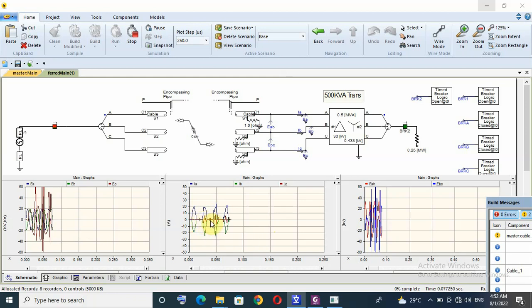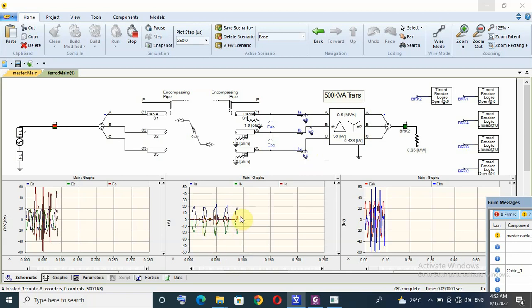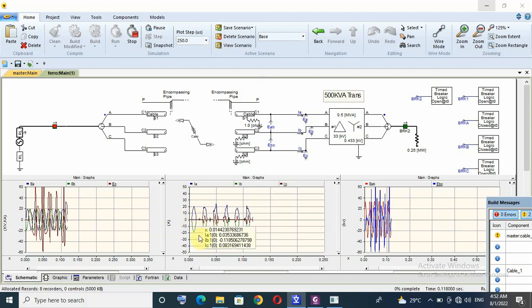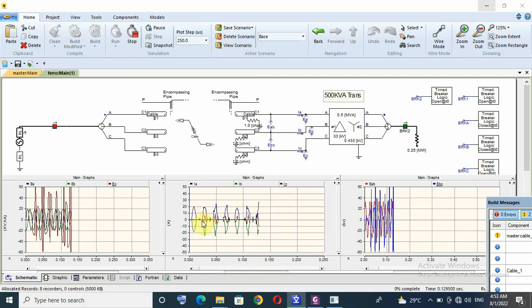For that, in differential protection or over current protection for transformer protection, we use this second order harmonic, or harmonic restraint to deactivate protection at the moment of inrush current. Because inrush current contain second harmonic order, second harmonic order is even order, and when even order occur, the waveform half cycle not the same as positive cycle, not the same as negative cycle. So here we have even order, even order harmonic.